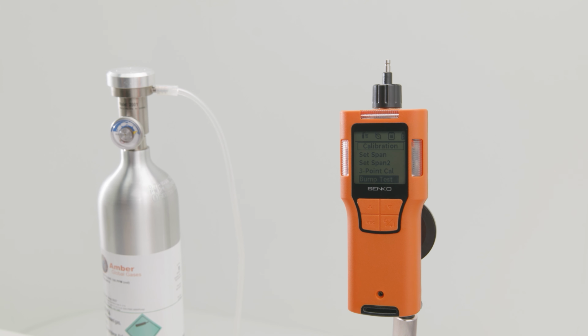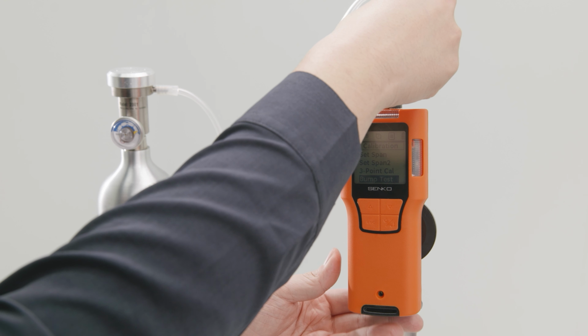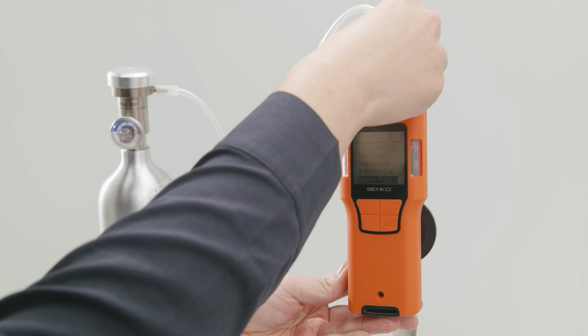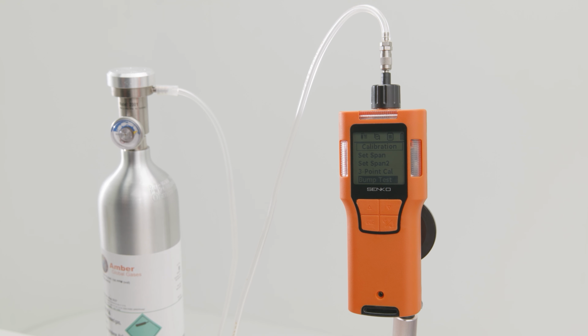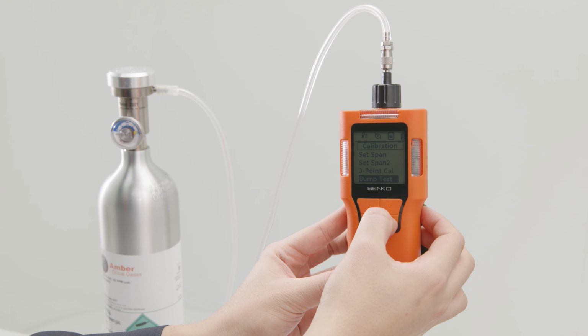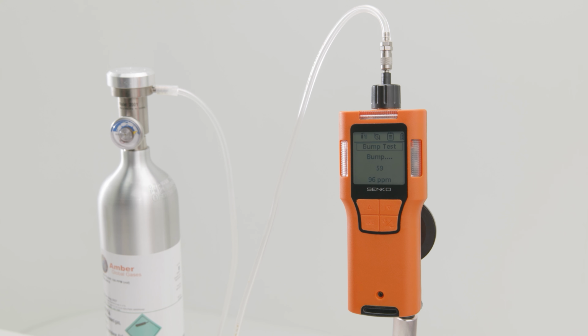A bump test is an inspection procedure to check whether the sensor and alarm function operate normally by reacting to gas, and it is not a test that evaluates measurement accuracy. By applying calibration gas at a concentration slightly higher than the low alarm threshold, you can check whether the alarm operates and whether the sensor responds.